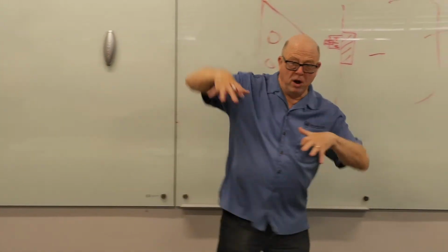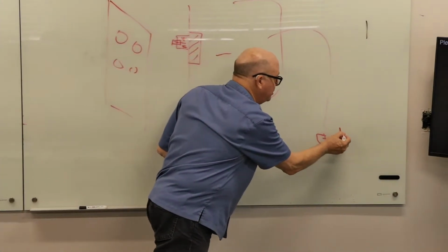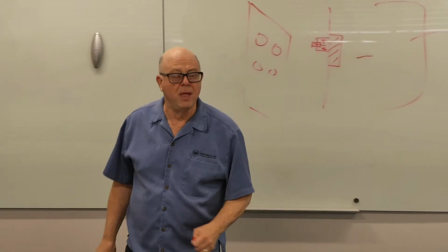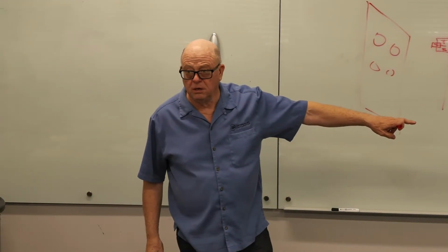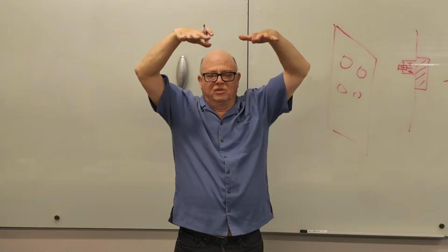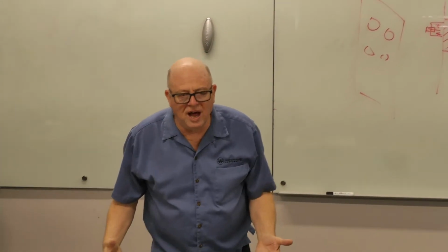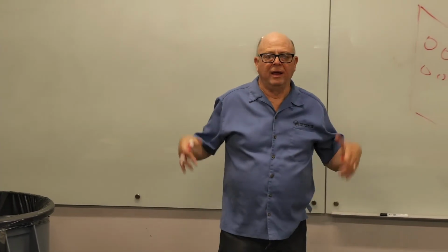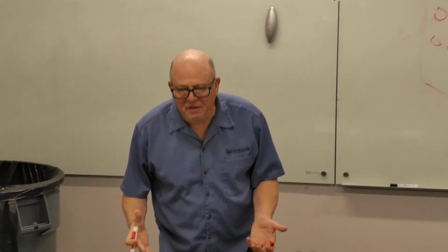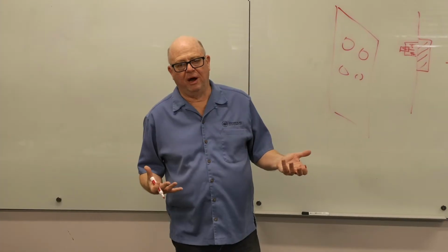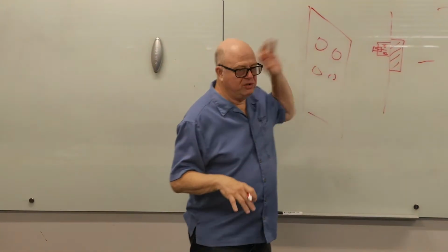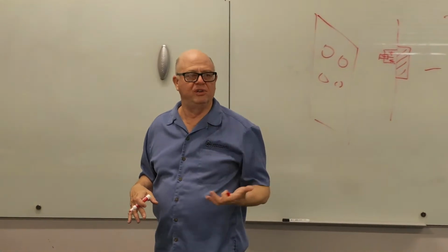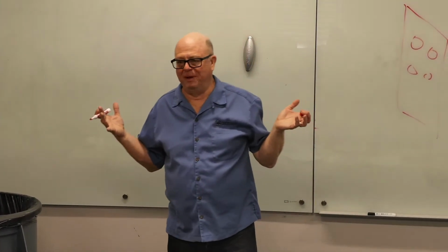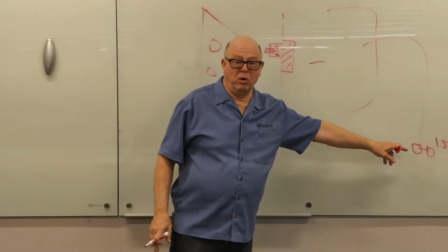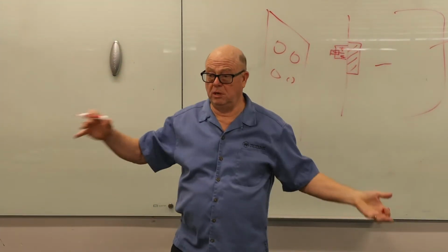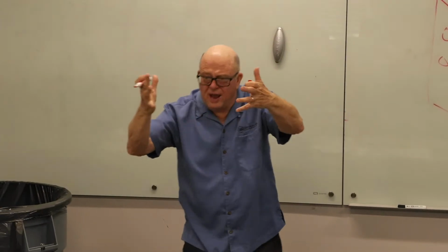And so part of your control logic is going to be, okay, if I want to maintain some number, whatever it is, adjustable, right? But if I want to maintain some number down there in the duct, first thing I do is, if it was at full speed, because it's morning cool down, it's Monday morning after the 4th of July, or Tuesday morning, whatever day people go back to work after a 3-day holiday in the summer, that building's going to be hot. As Mr. Sanderson pointed out previously, Title 24 says you get up to some temperature and you start pre-cooling, but people often disconnect that because, hey, that's money I have to spend. Nonetheless, you come in some Monday morning and it's hot, and so all your fans are going to be going full tilt boogie, cooling off the building until the building gets down to a reasonable temperature. And then they'll start to back off.